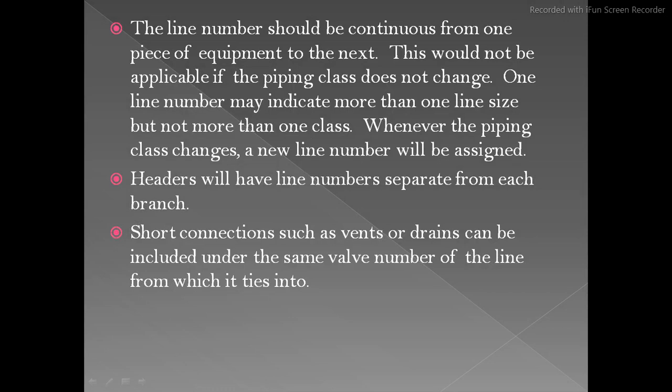The line number represents connectivity between equipments. This would not be applicable if the piping class does not change. One line number may indicate more than one line size, but not more than one class. Whenever the piping class changes, a new line number will be assigned.